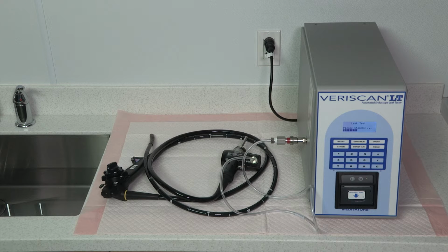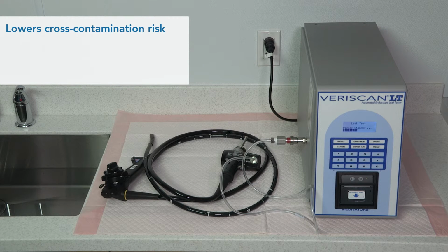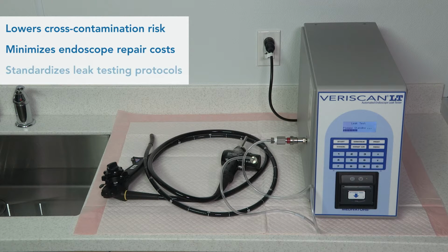The VERISCAN Leak Tester is designed to meet customer needs by providing the following benefits: lowers cross-contamination risk due to undetected leaks and bacteria invasion by using highly sensitive and extremely accurate leak sensing technology. Minimizes endoscope repair costs through early detection of leaks before submersion in fluid, and standardizes endoscope leak testing protocols, which drives compliance.